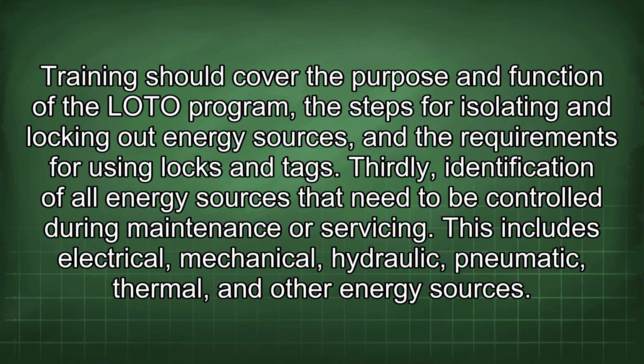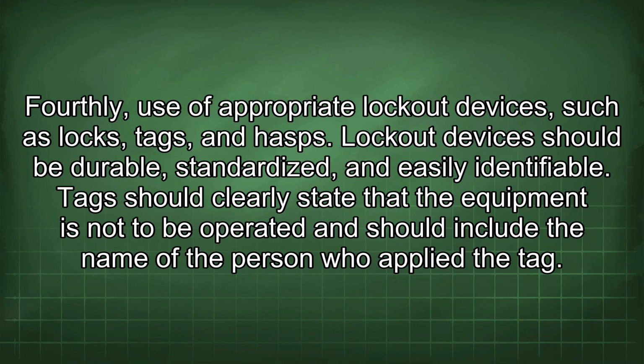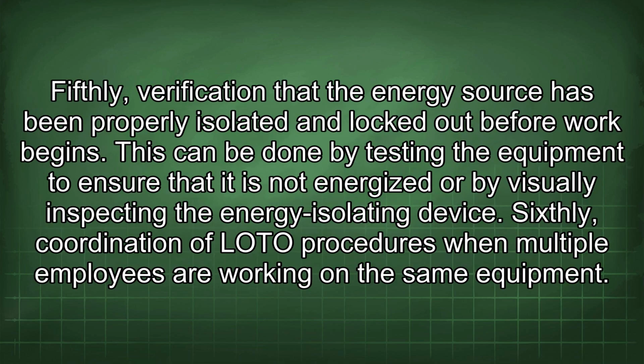Thirdly, identification of all energy sources that need to be controlled during maintenance or servicing. This includes electrical, mechanical, hydraulic, pneumatic, thermal, and other energy sources. Fourthly, use of appropriate lockout devices, such as locks, tags, and hasps. Lockout devices should be durable, standardized, and easily identifiable. Tags should clearly state that the equipment is not to be operated and should include the name of the person who applied the tag. Fifthly, verification that the energy source has been properly isolated and locked out before work begins.